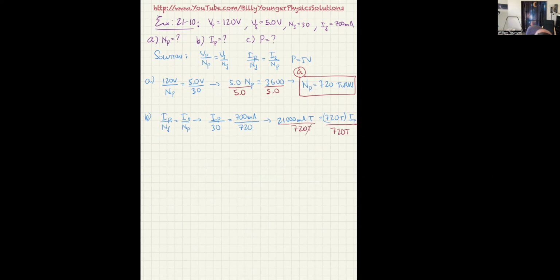You can see the turns cancel out here, just like they cancel out here, and basically I get 21,000 divided by 720. So I primary is equal to 29.17, or actually 17 milliamps. Again, it came out in milliamps because we put it in milliamps. If we put it in kiloamps, it would come out in kiloamps, and if we put it in amps, it would come out in amps.